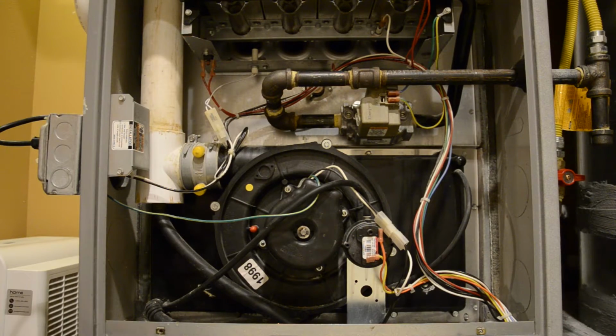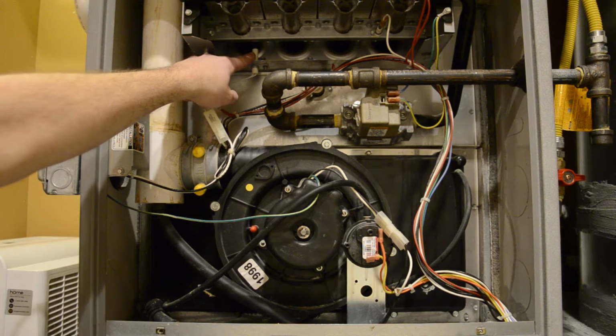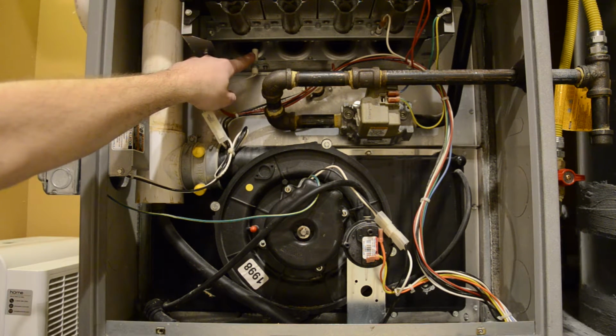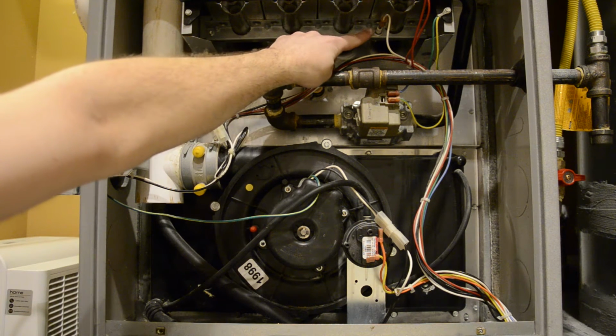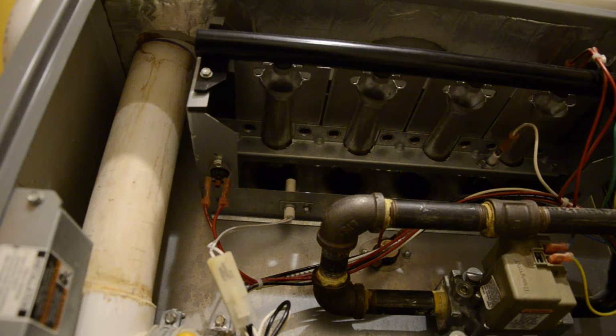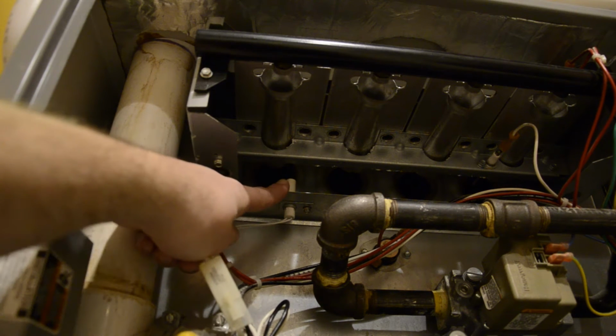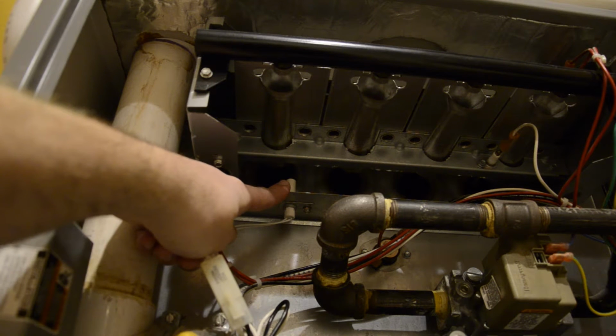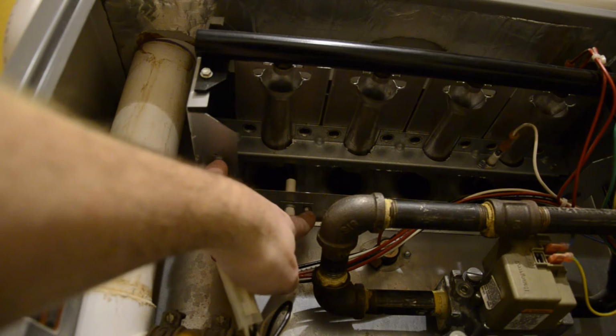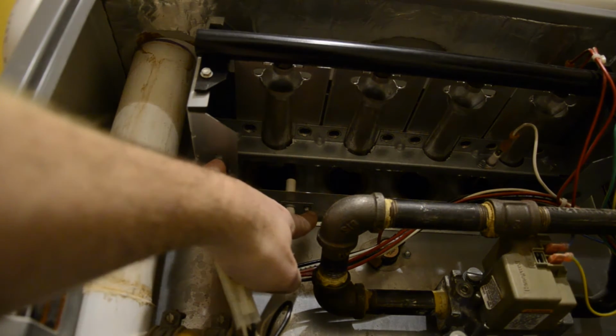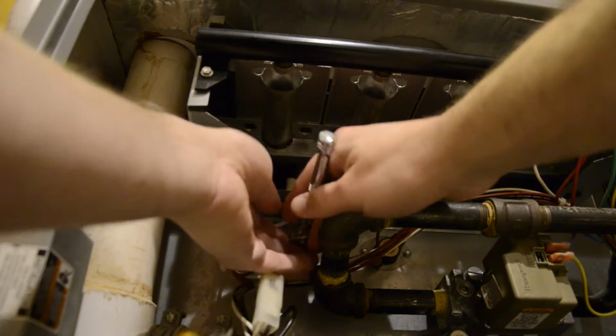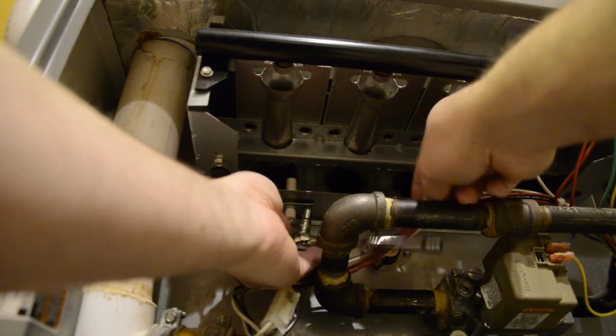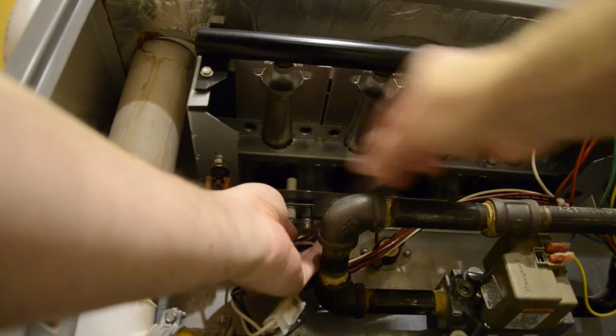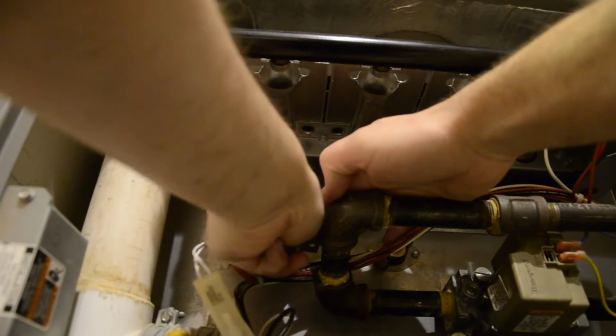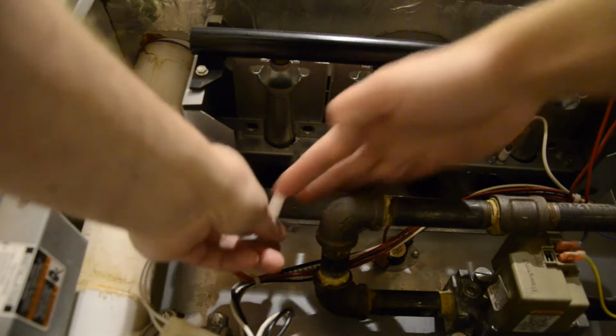Two common reasons for the furnace not working are the igniter being cracked or the temperature sensor having too much carbon buildup. The igniter is located here in front of the combustion tubes. To remove it, remove the small screw. After the screw is removed, pull out the igniter.